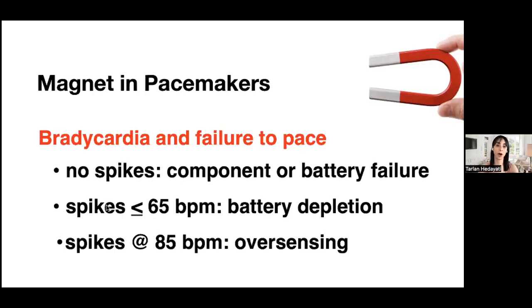If you put the magnet on and start to see spikes, but they're slow—under 65 beats per minute—it means the battery is reaching the end of its life, and the pacemaker is trying to preserve its battery, so it's not working as frequently as it should. If you put the magnet on and get spikes at 85 beats per minute or higher, something interfered with the pacemaker, usually oversensing, and now you've got the pacemaker back online and all is well. That's what happens when you put a magnet on a pacemaker in the setting of bradycardia or failure to pace.